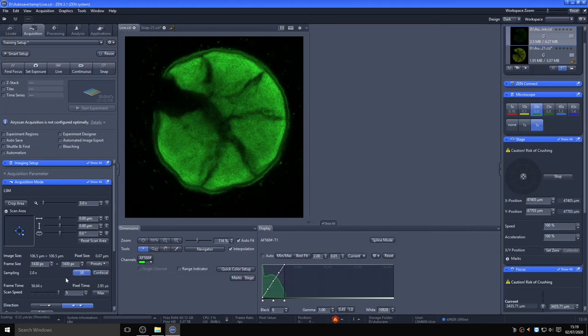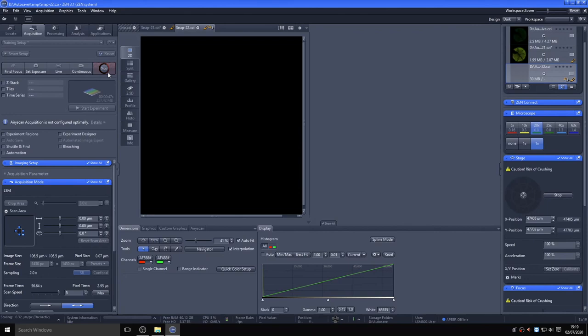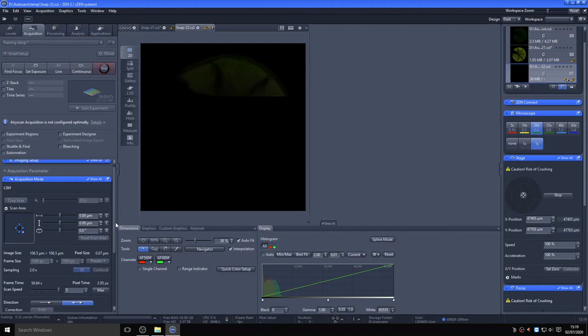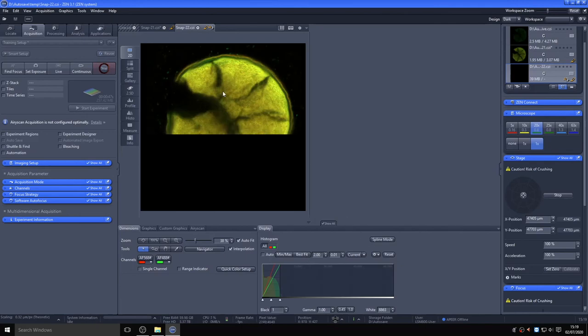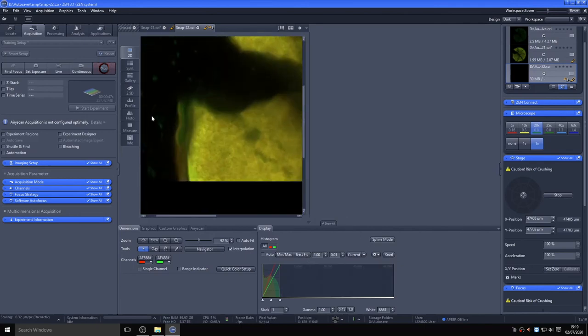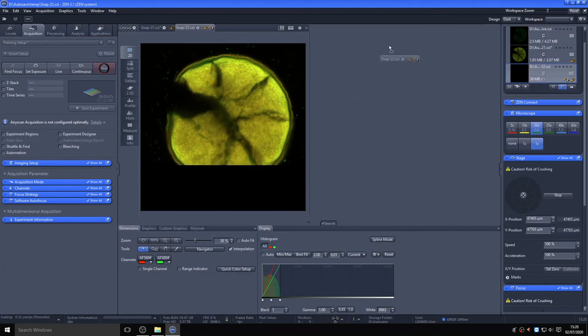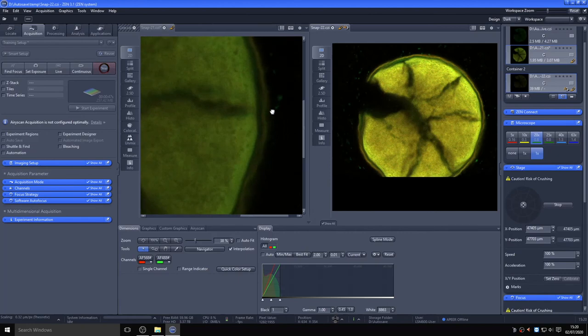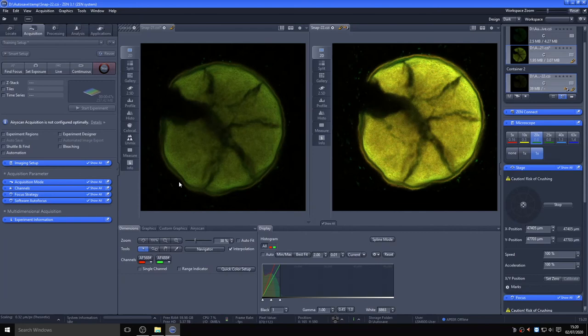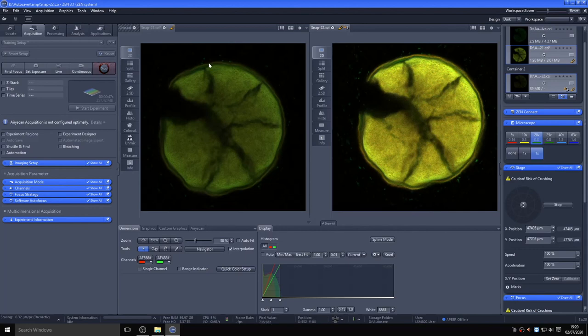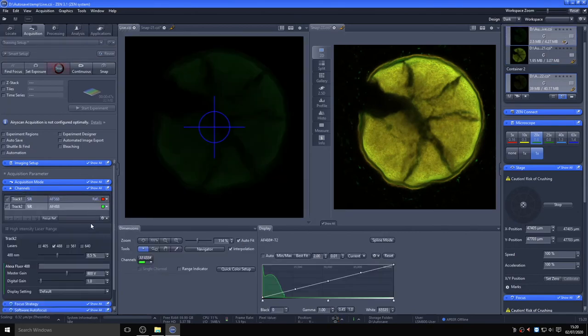Not only is extra data being collected, but it is being reassigned where the fractionally different angles at which the light hits each of the detectors in the array is used to mathematically calculate extra resolution. You can also see a warning that Airyscan acquisition is not configured optimally. Hovering over this will explain why. In this case, for best resolution, the system suggests using the 63x lens rather than the 20x. It will also warn if your pixel sizes are too large for optimal acquisition and Airyscan calculation. However, the advantage of Airyscan over some of the other super-resolution techniques is the ability to use any lens and fluorophore on live or fixed samples. You can see if you compare the confocal image we previously took with the sum channel, they look very similar. However, when the data is processed in the SR tab, you can see the increased resolution offered by Airyscan compared to confocal.